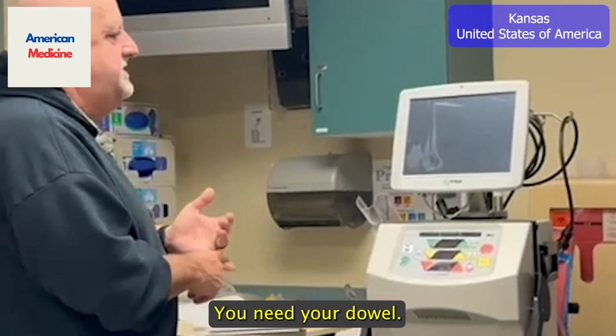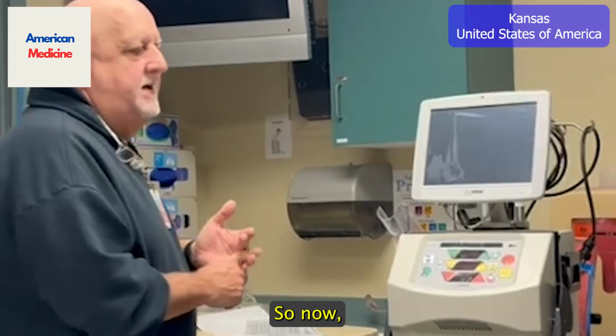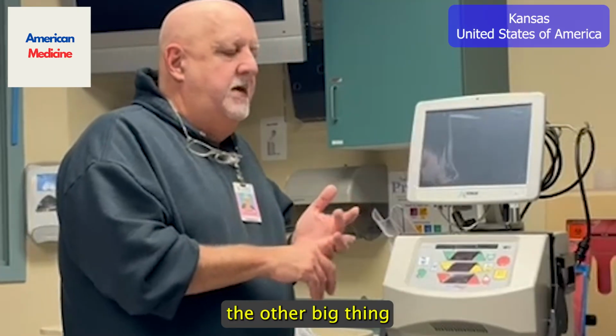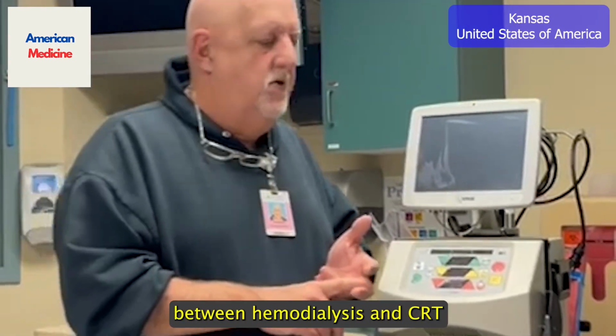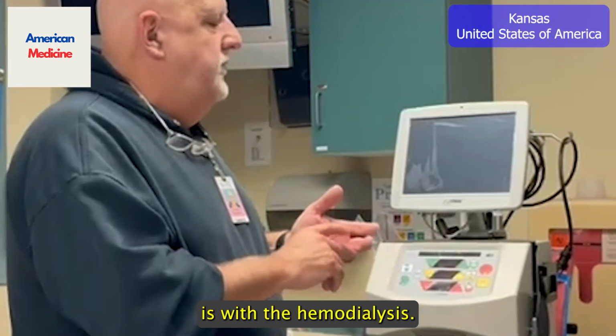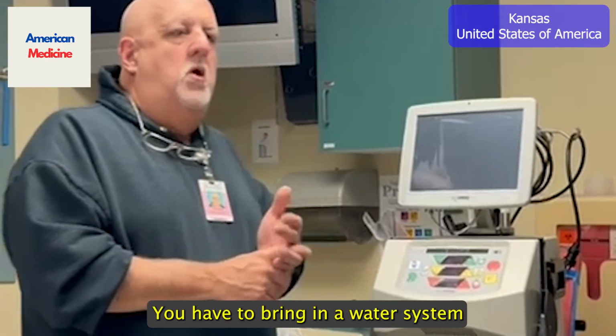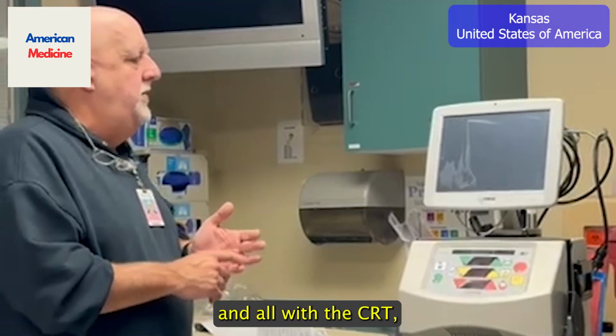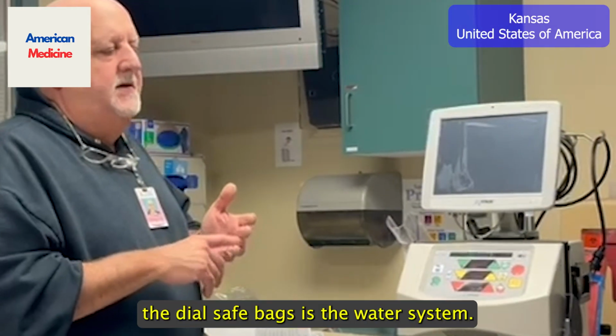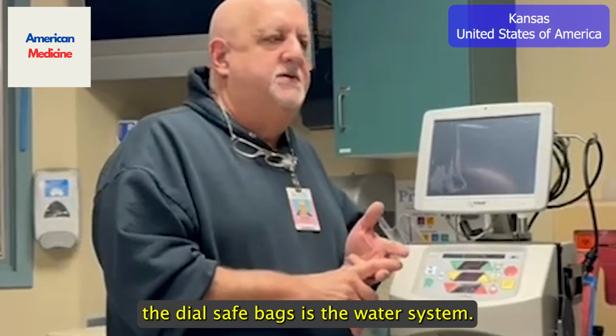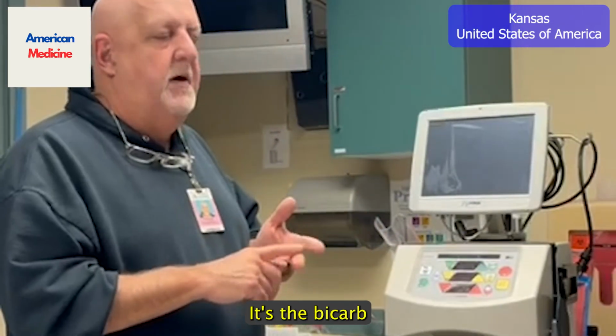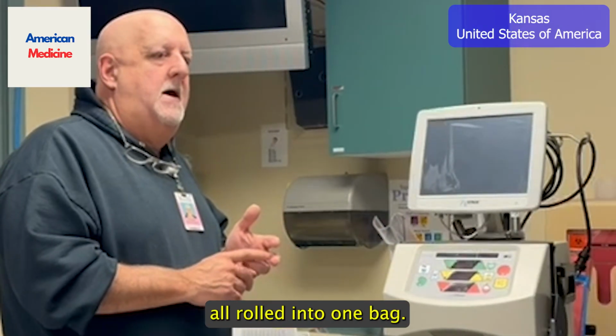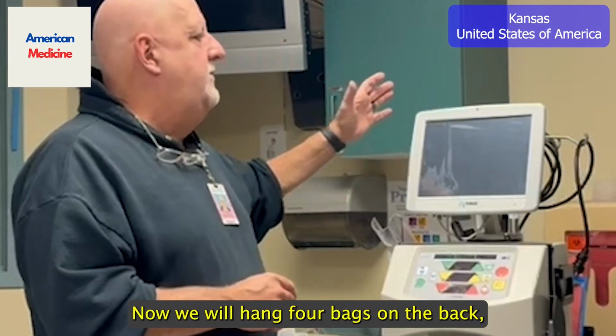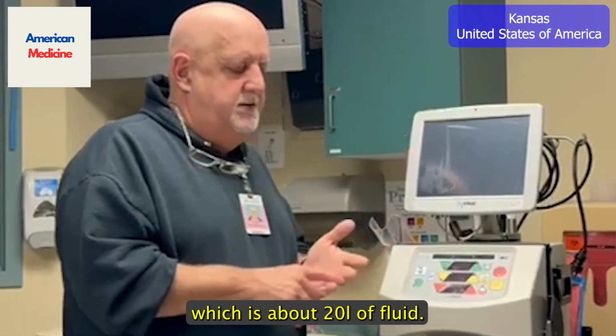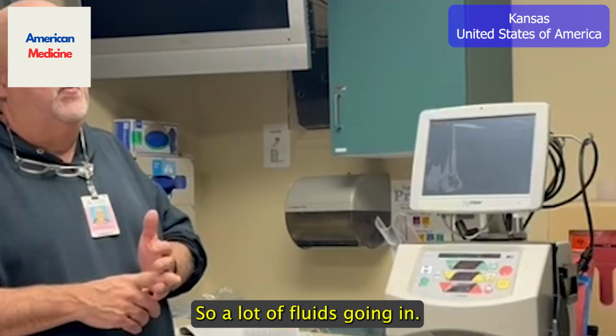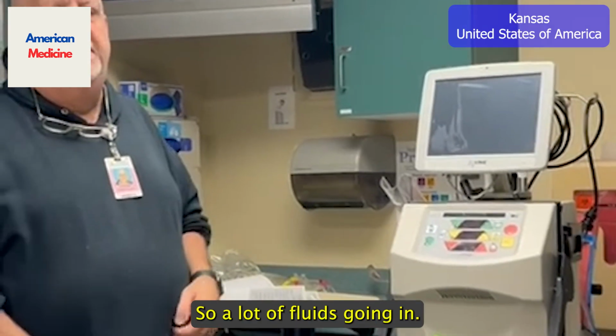need your cartridge setup. You need your dialysate. Now, the other big thing between hemodialysis and CRRT is with the hemodialysis, you have to bring in a water system and all. With the CRRT, the dialysate bags is the water system, it's the acid, it's the bicarb, all rolled into one bag. Now we will hang 4 bags on the back, which is about 20 liters of fluid. So a lot of fluids going in.